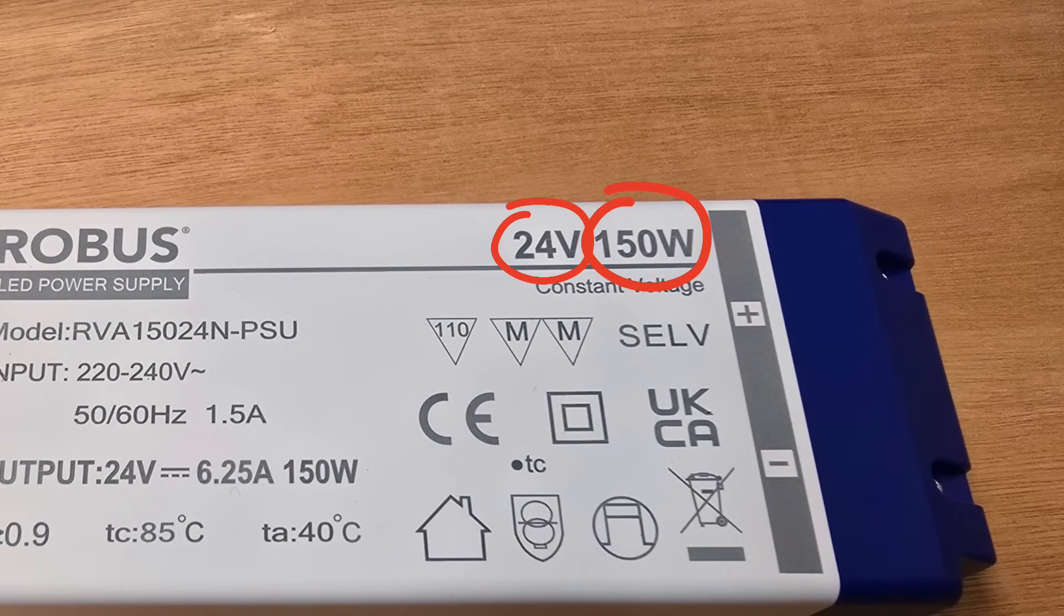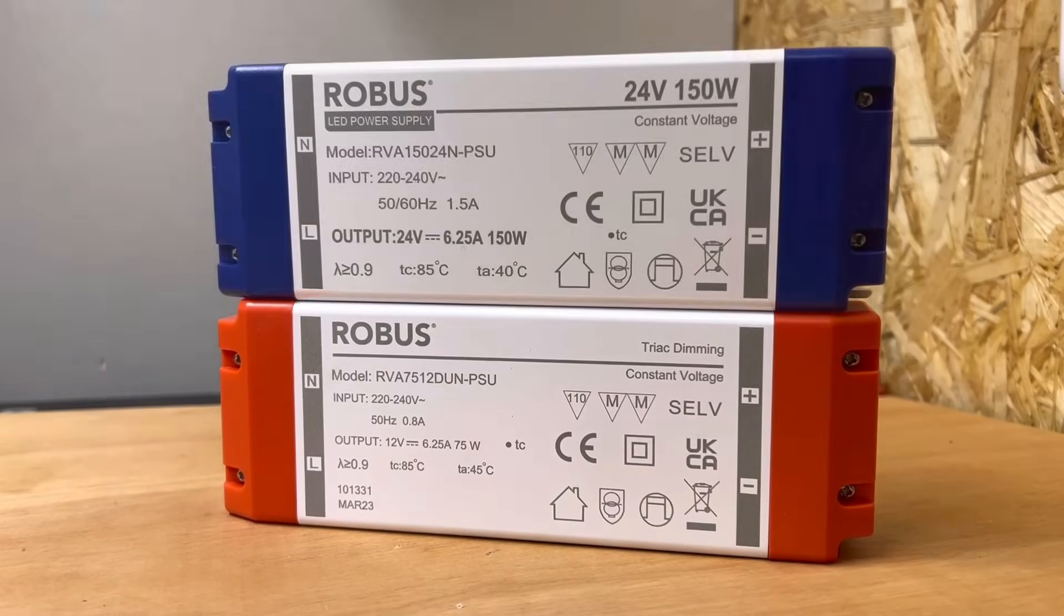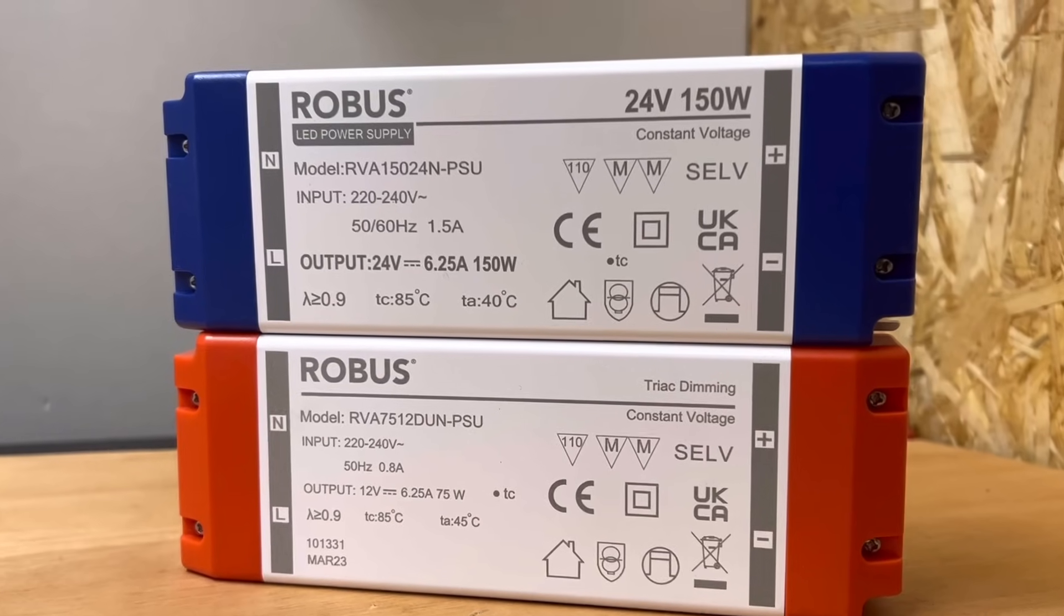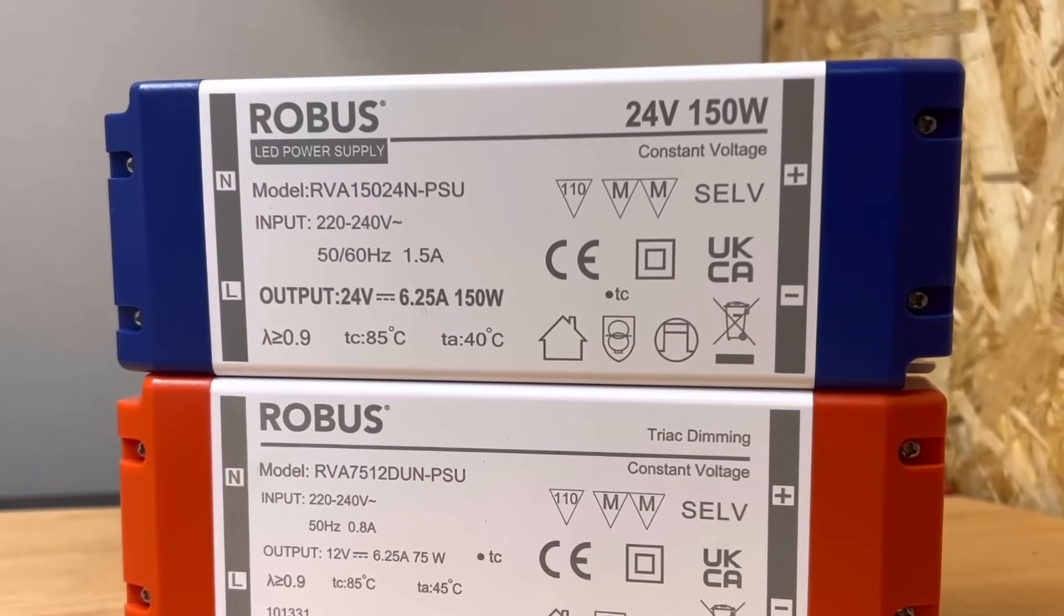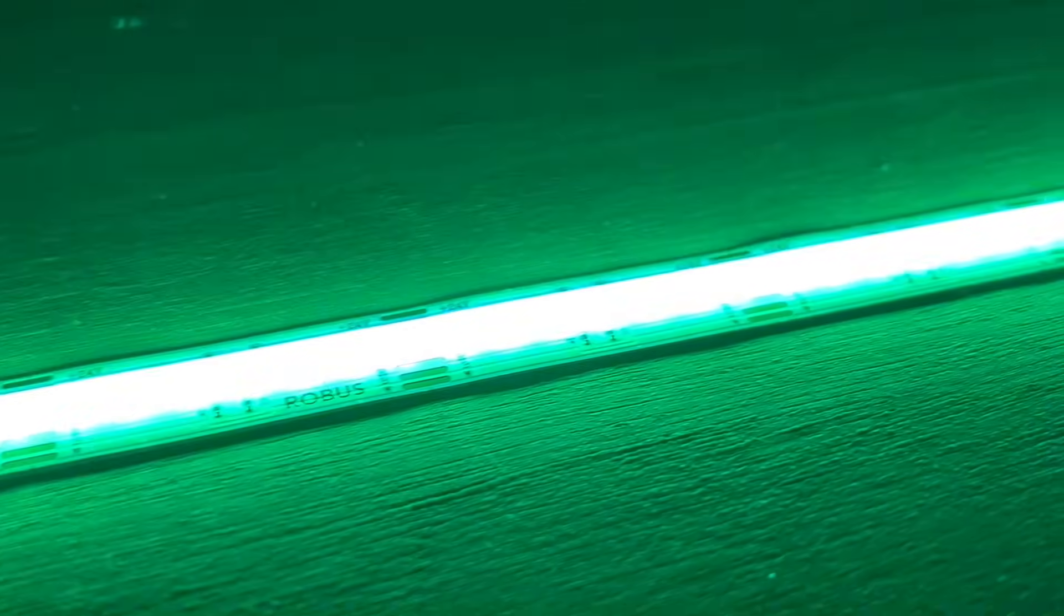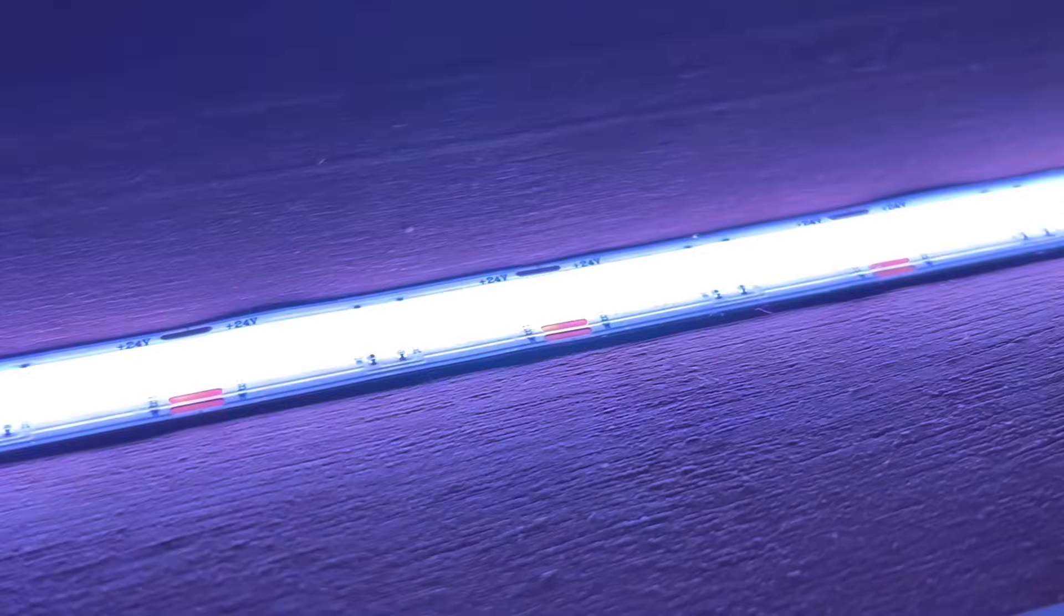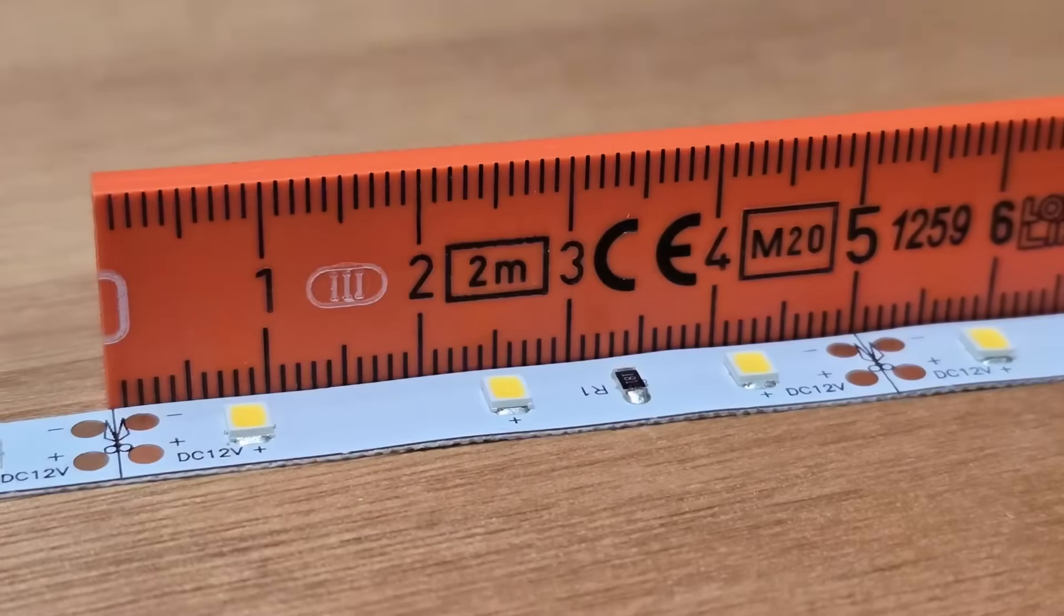We're going to cover the voltage aspect in the next video in this series, so for now it's enough to know that there are two main voltages used for LED strips: there's 12 volts and 24 volts. While you'll find either of these used in both domestic and commercial installations, 24 volts is the most commonly used because it can run efficiently on lower currents, reducing volt drop issues.